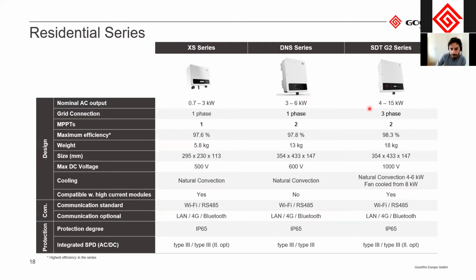Later or after that, we enter the 3-phase inverters, and this is called SDT Generation 2, and this ranges actually from 4 up to 25 kilowatt, but within the residential segment, we have it between 4 and 15 kilowatt. And the difference here also for the residential STT G2 inverters is that it has a maximum DC input of 1000 volt instead of 1100, which is for the 17 kilowatt up to 25.